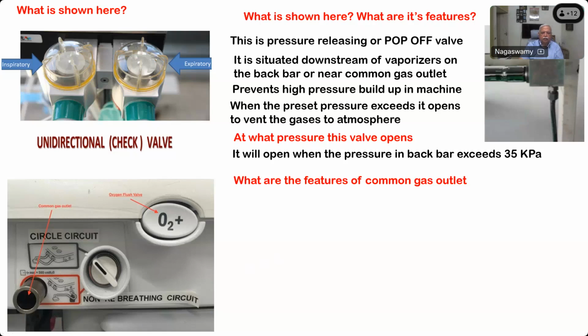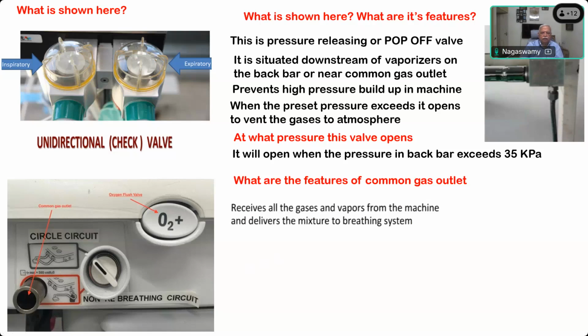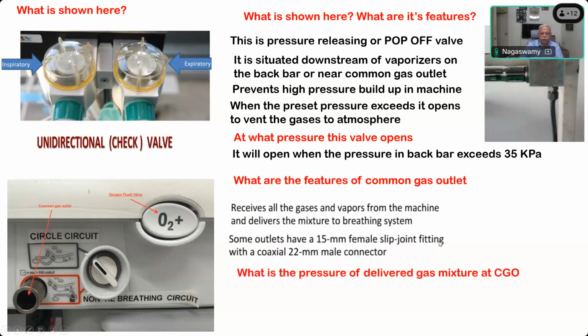What is the diameter of the common gas outlet? It receives all gases and vapors from the machine and delivers the mixture to the breathing system. That is the purpose of the common gas outlet, number one. Some outlets have a 15 mm female slip joint fitting with a coaxial 22 mm male connector. These two numbers are very common in all breathing system adapters. So this fits tightly without leakage or slippage.